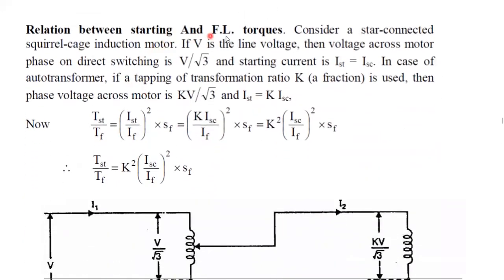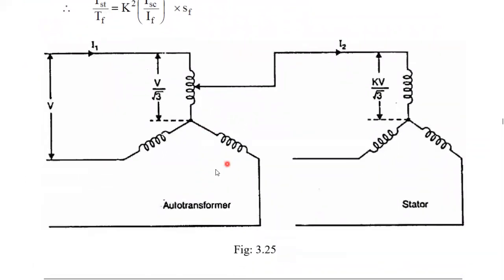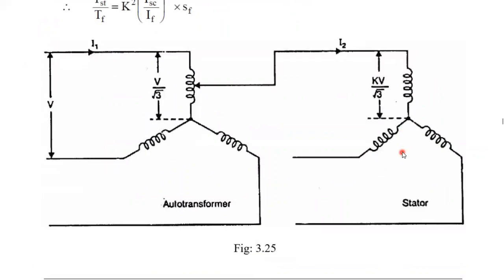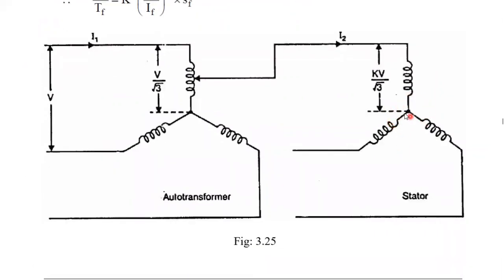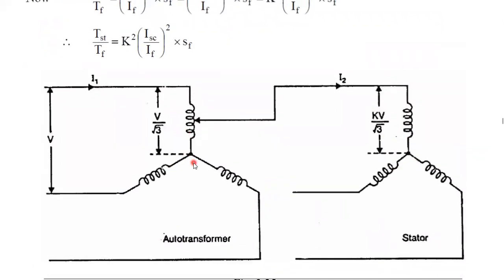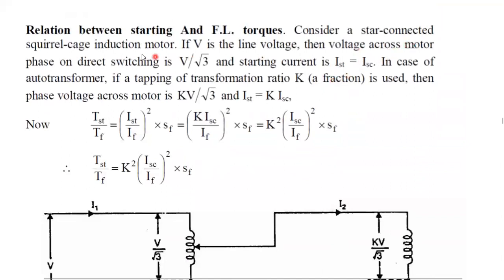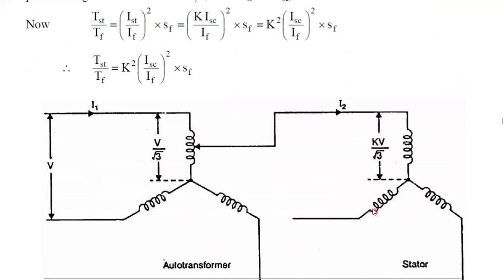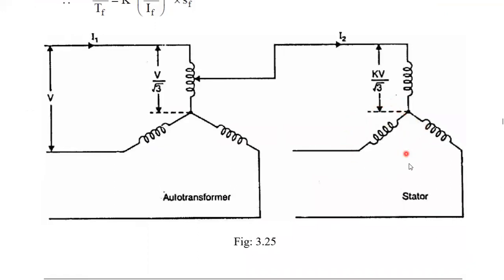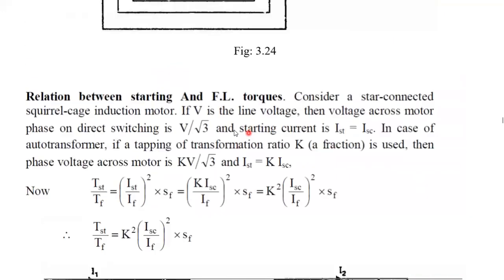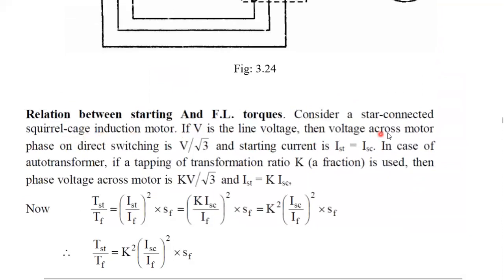And here is the relation between the starting and full load torques in auto transformer starting. Auto transformer starting is used for both star and delta connected motors. The stator winding of the induction machine is connected in star, and the auto transformer winding is also connected in star. Understood? Consider a star connected squirrel cage induction motor, where the stator winding is star connected.